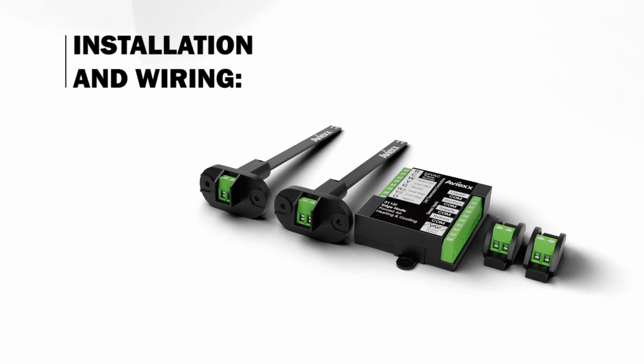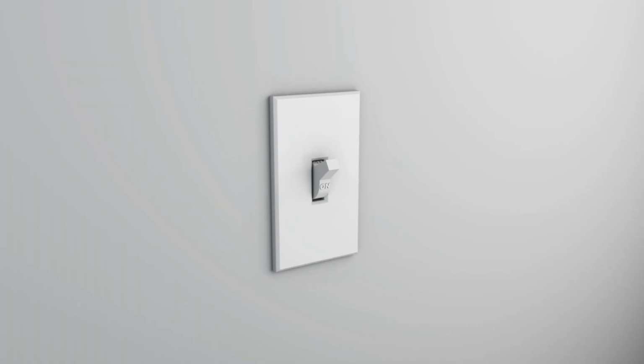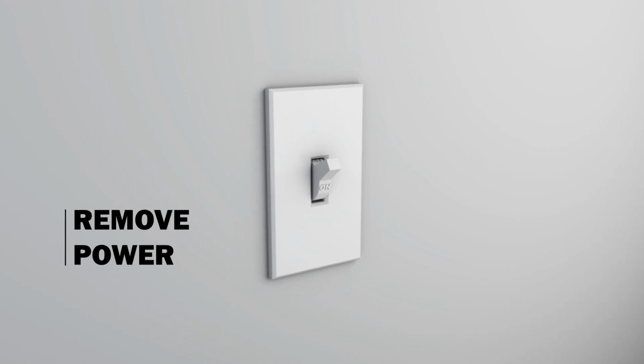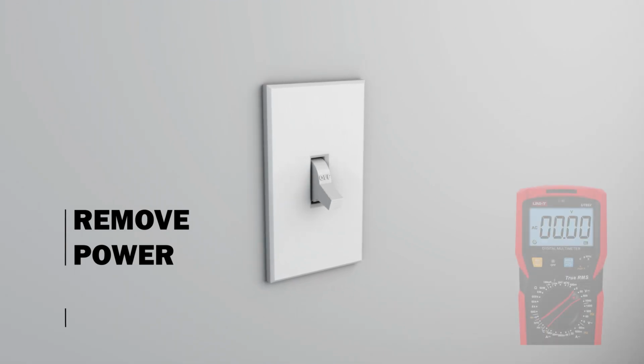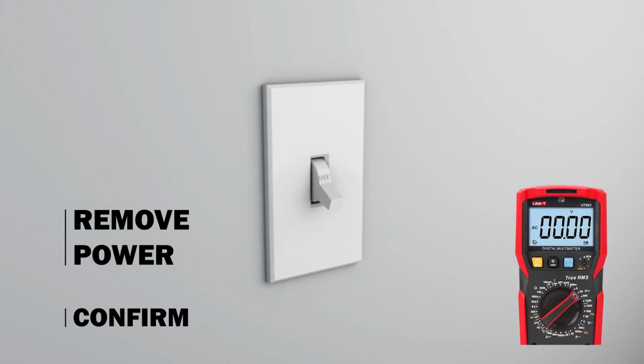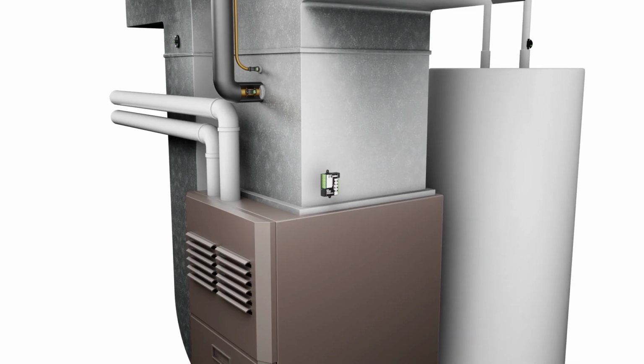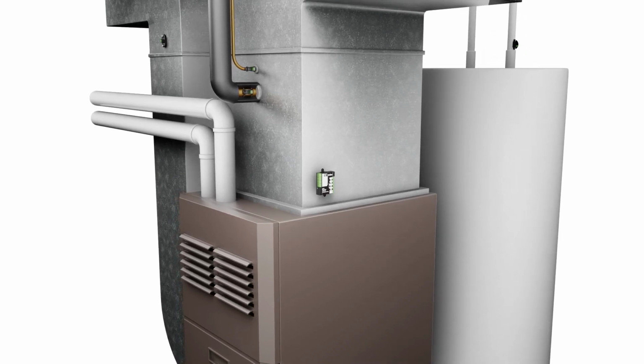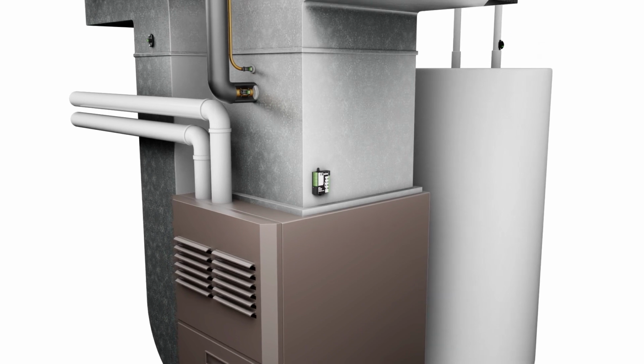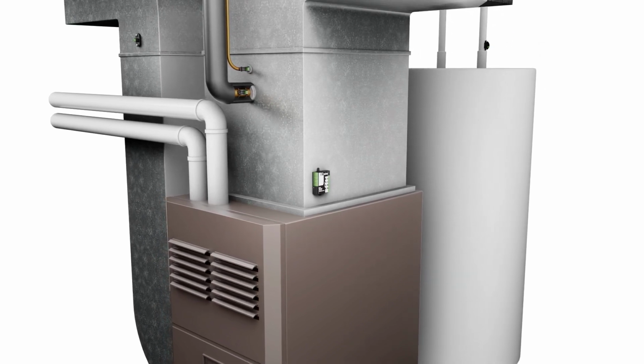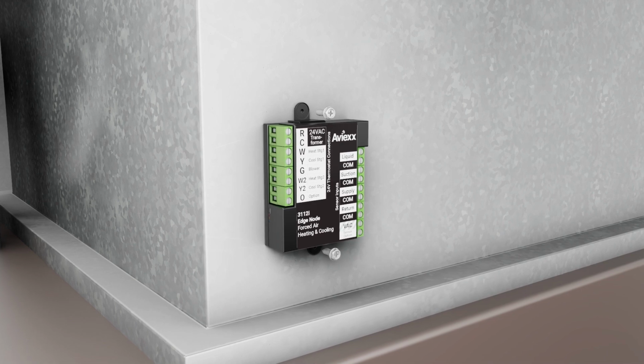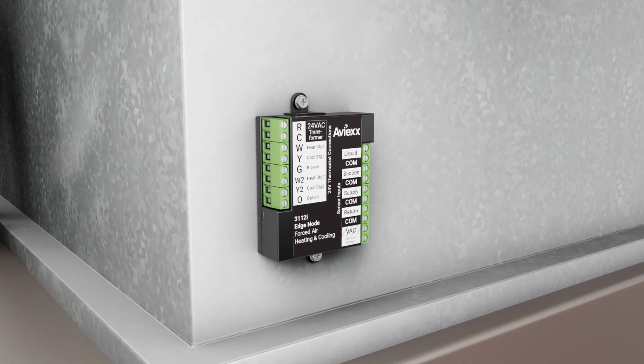Installation and wiring of the Aviexx Edge node. Begin the installation process by removing power from the HVAC equipment. Confirm that the 24-volt AC circuit is de-energized. Position the Aviexx Edge node in a convenient place on the exterior of the equipment that is safe, dry, and secure. Using self-tapping screws, attach the node to the equipment.